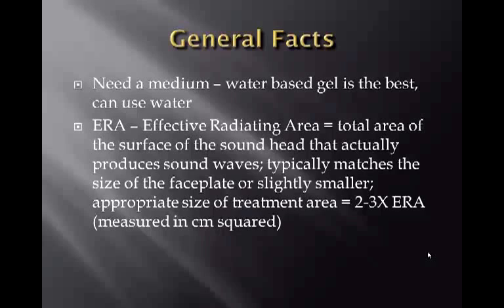ERA is the effective radiating area. This is the total area of the surface of the sound head that actually produces sound waves. It typically matches the size of the faceplate or is slightly smaller. This allows you to decide what your appropriate size of treatment area is, and it's going to be two to three times the size of the faceplate or the effective radiating area. It's measured in centimeters squared.